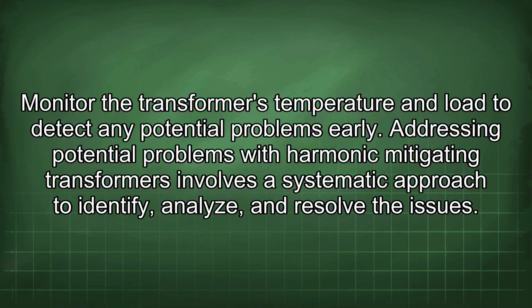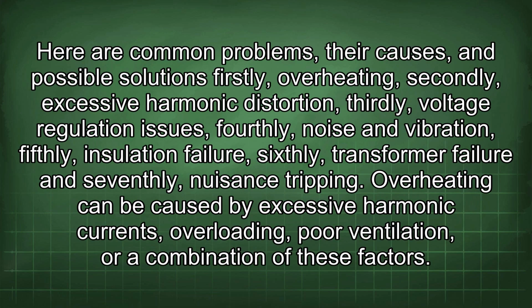Addressing potential problems with harmonic mitigating transformers involves a systematic approach to identify, analyze, and resolve the issues. Here are common problems, their causes, and possible solutions. Firstly, overheating. Secondly, excessive harmonic distortion. Thirdly, voltage regulation issues. Fourthly, noise and vibration. Fifthly, insulation failure. Sixthly, transformer failure. And seventhly, nuisance tripping.